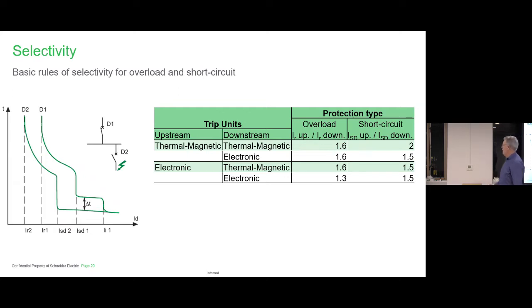This is wherever you see basic rules or general comments, please utilize this. It's a nice one. It just says between a thermomagnetic and a thermomagnetic, your target is to have something like 1.6 times the current between them. If you get that, you're likely to get selectivity, total selectivity. And for the short circuit side of it, it needs to be a minimum of 2 times. Often it has to be higher, but at least 2 times. So as long as you apply that, and we've given other examples, thermal to electronic, and vice versa, and you'll see when you have electronic to electronic, see how the number's lower?